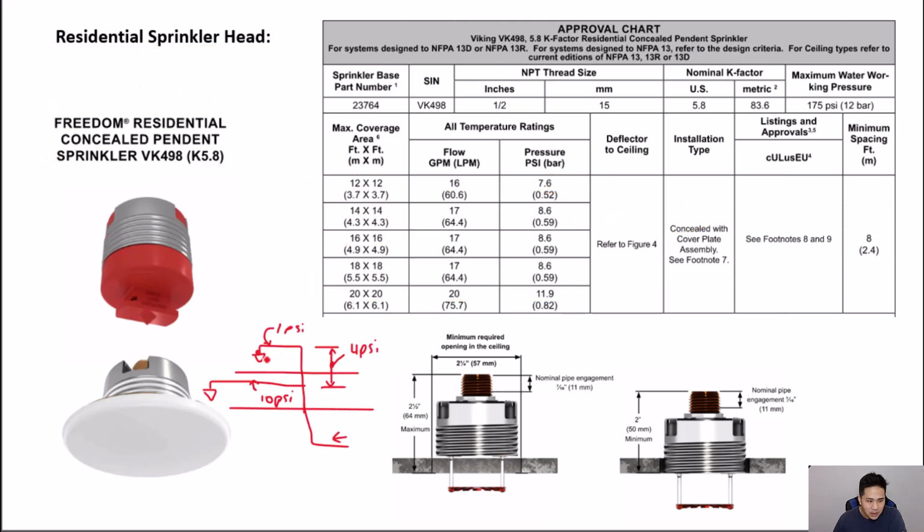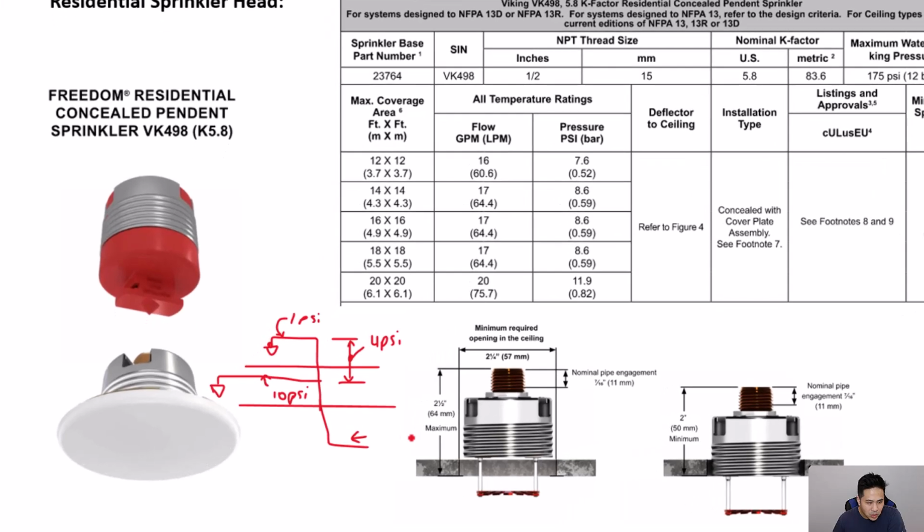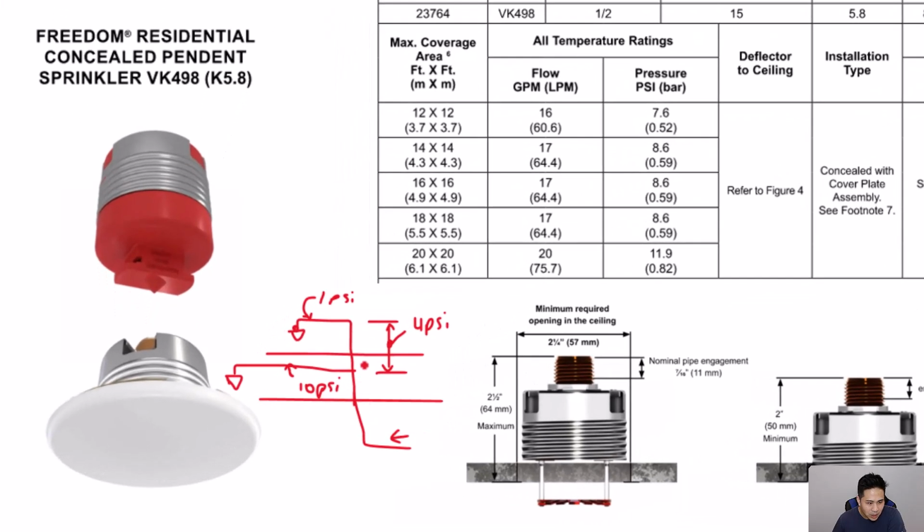And when I state the most demanding sprinkler head hydraulically, it does not necessarily mean it's at the highest and furthest point. I'm going to try to demonstrate in this example here. So we have a water service that comes in this way. It goes up. This is the elevation. So let's say that these are the floors, and this is the top floor that it's on.